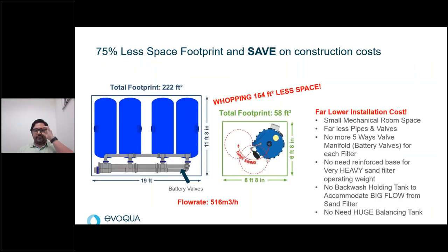So what does that mean? This is an example. One unit of our largest Defender filter can cater up to 516 cubic meters per hour, where sand filter would need 4 units of horizontal filter to cover that flow. So when you have smaller numbers of equipment, you have no need for many pipes and no need for many valves.